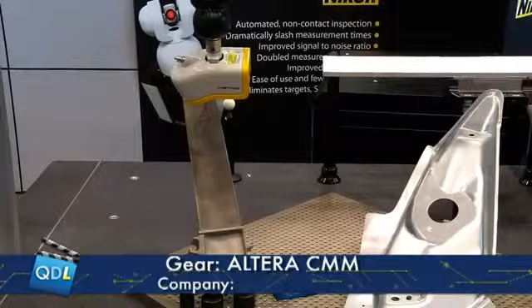Moving on to the machine, one of the aspects is the material. This material is quite unique within the CMM industry. It's ceramic. A lot of competitors use aluminium, and aluminium tends to be less stable over time. These machines go into working environments, so temperature changes and shifts affect the accuracy of the machine. So ceramic is the preferred material. Ceramic is a very stable machine, not only in temperature shifts, but over a long period of time. And we guarantee the accuracy of these machines for 10 years. We guarantee that the accuracy the machine gives on day one will still be there after 10 years. If not, we will put that right.